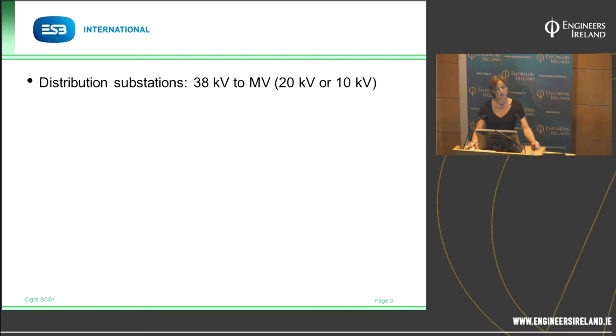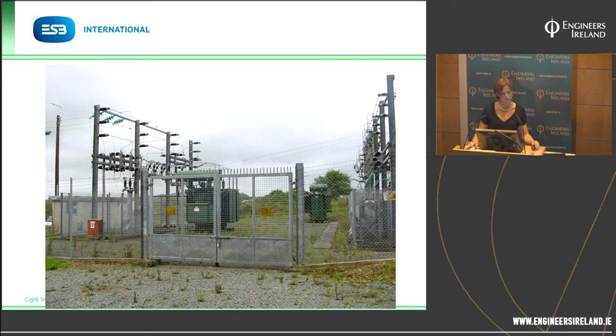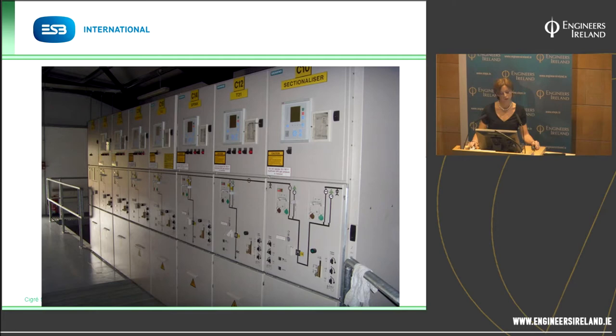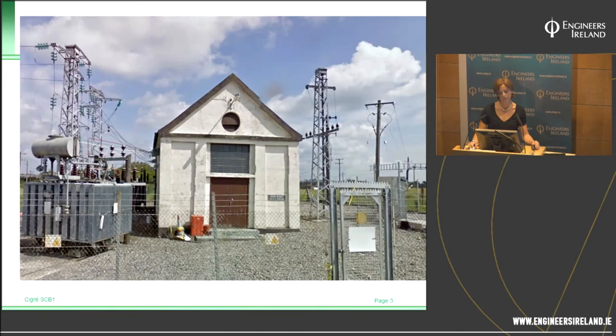Now, in Ireland, a distribution substation operates at 38 kV stepping down to MV, which is at either 10 or 20 kV. There's approximately 500 of them in the country. Each one would feed a mid-sized town with up to maybe 5,000 customers on it. There are three types of stations. There's an outdoor, where the 38 and MV is outdoor AIS, air insulated switchgear. Hybrid stations, where the 38 kV is outdoor AIS and the MV is indoor GIS, gas insulated switchgear. And indoor stations, where both the 38 and the MV is indoor AIS.